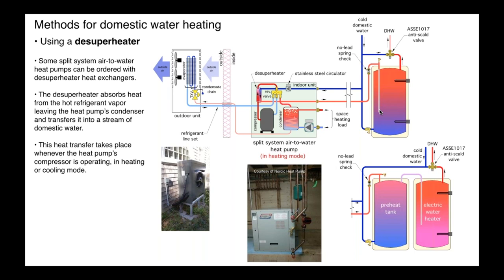We still have to take that refrigerant gas coming off that compressor, and we have to lower its temperature to the point where it will start to condense. That's what de-superheating means. So we're scavenging, at nominal numbers, about 10% of the capacity of the heat pump, and putting that in the domestic water tank.